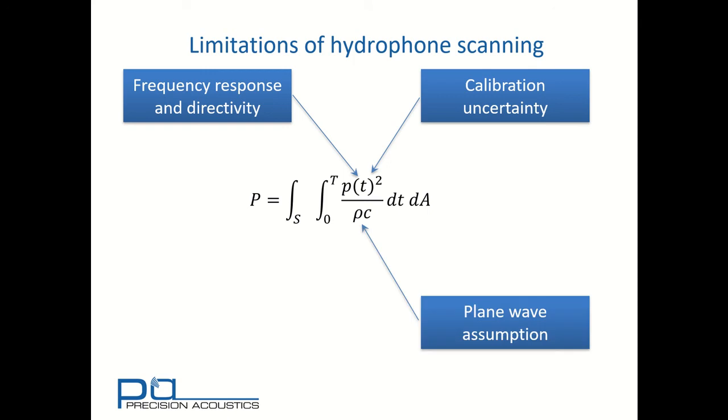And in order to convert from a pressure to a time average intensity signal, we've had to make use of the plane wave assumption, which may or may not be appropriate for the field we're considering. Finally, there may be positional inaccuracies, or we may have insufficiently sampled the field when we defined our measurement locations.